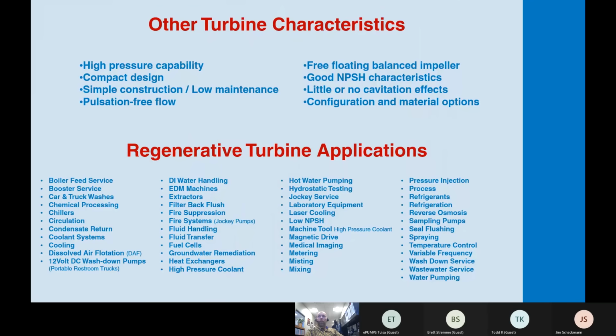Anyway, pulsation free flow, free floating balanced impeller means that it's not going to wear as quickly because it doesn't touch. As the impeller is turning, it does not touch the walls of the casing or motor bracket. And regen turbines have very good NPSH with little to no cavitation. Because of the way they work, all of the pressure stays on the peripheral of the impeller, which I'll show you here in a moment. And as a result, there's not much cavitation, so we could be put into higher temperature situations, all the way up to boiling temperatures, and still be running at very low NPSH, where a lot of multi-stage centrifugals cannot because of cavitation.